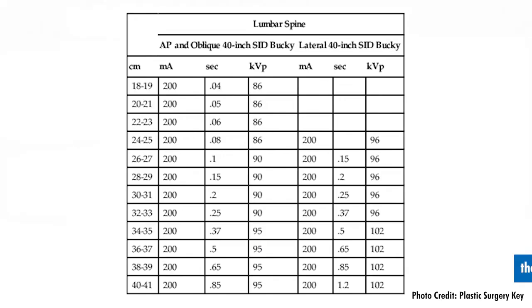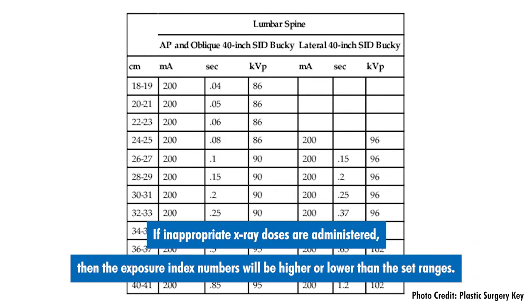This measurement is contrasted to a scale that can be interpreted as too much or too little radiation. These indices yield numerical ranges that are regarded as within normal limits. If inappropriate x-ray doses are administered, then the exposure index numbers will be higher or lower than the set ranges.